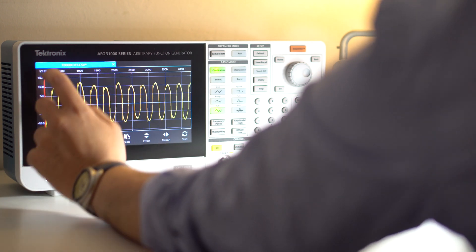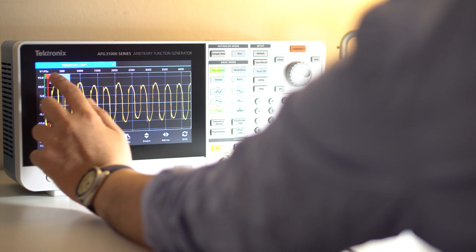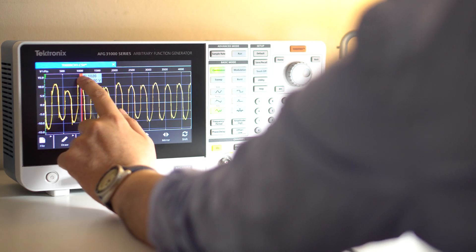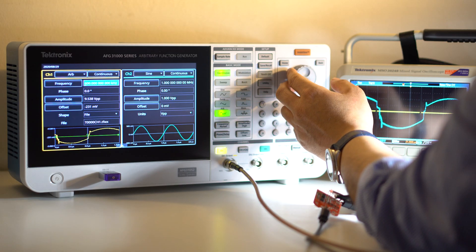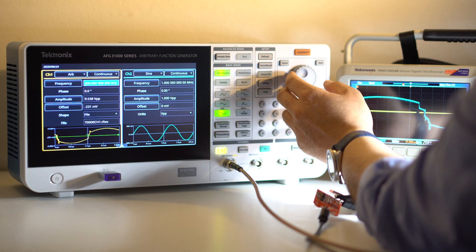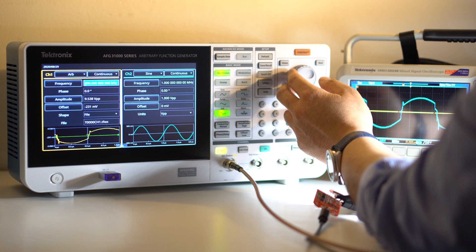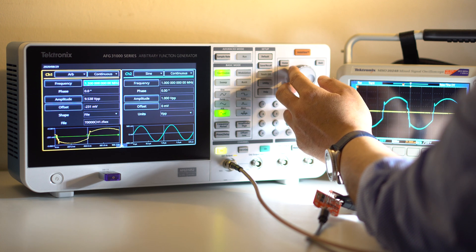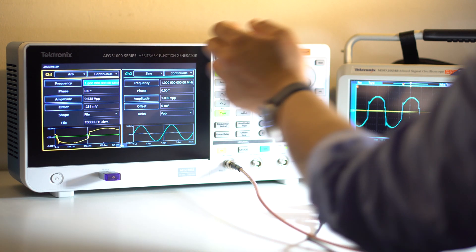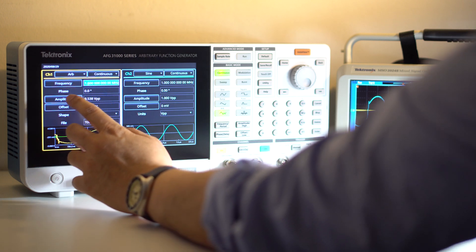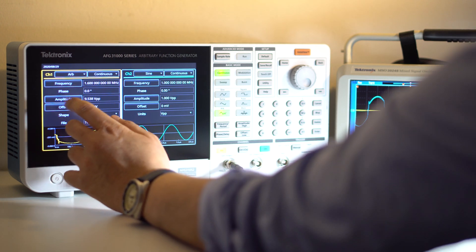Once a waveform has been created, you can use either the basic or the advanced mode to play that waveform out. And there it is, the scope is now seeing the signal from the AFG31K. I can change the frequency and amplitude and offset, just as if it were a built-in standard waveform.